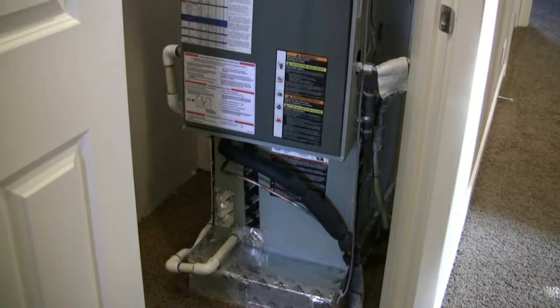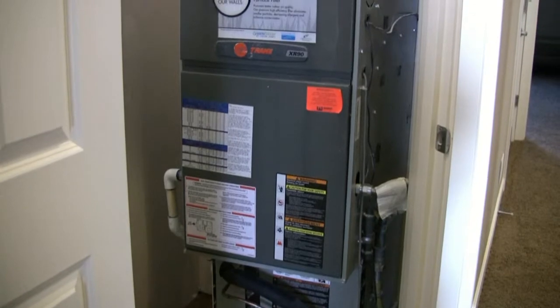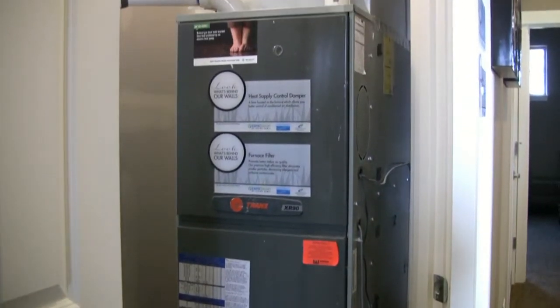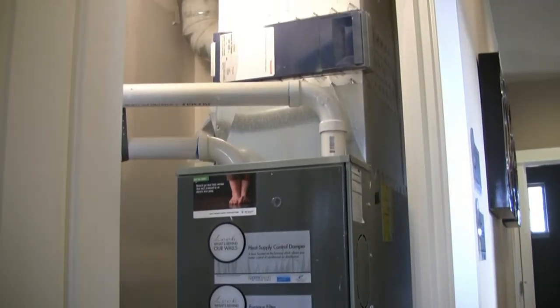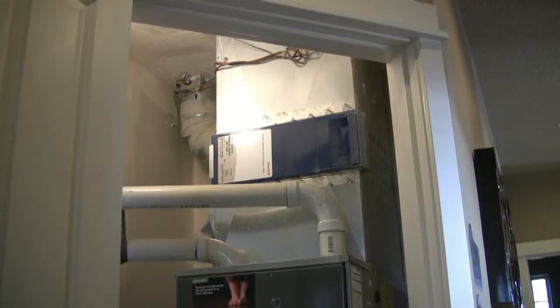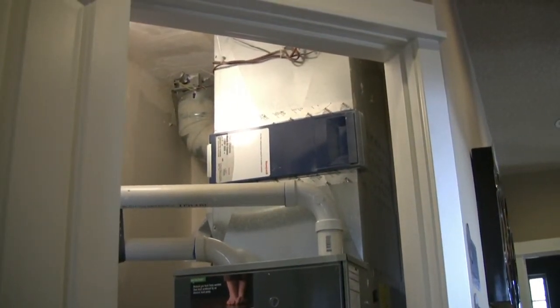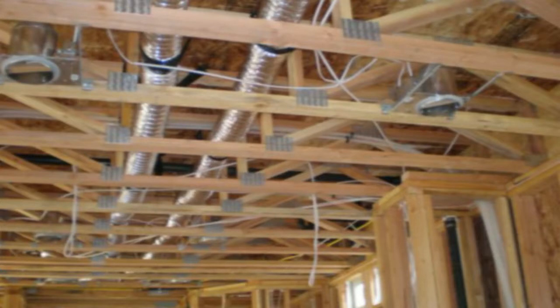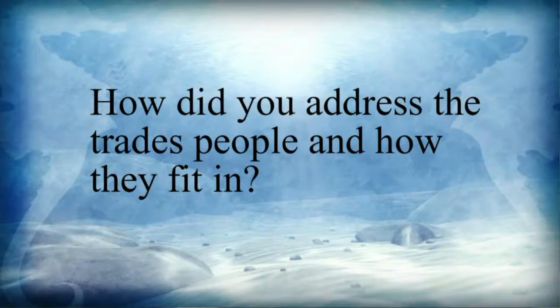We use a downdraft furnace mounted on the second floor, and we drop it into a plenum box that's in between the floor joists. From there we have a main trunk line that runs, in this case, crossways or parallel to the floor trusses, and then we have the individual heat ducts that come off of that. It was imperative that we had open web trusses so that we weren't tied down to one or two places to run ductwork. With the open web trusses, we could virtually run ductwork anywhere we wanted to.